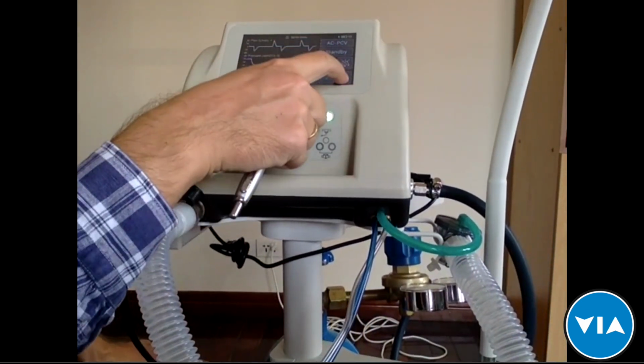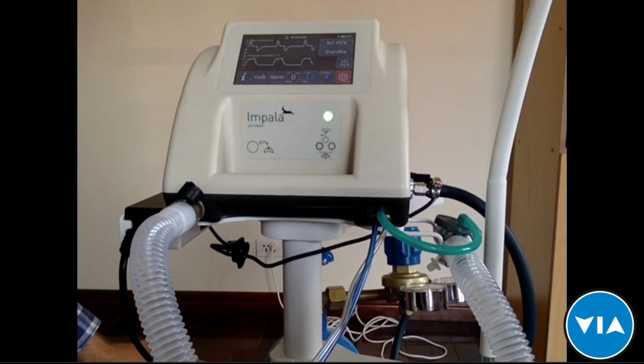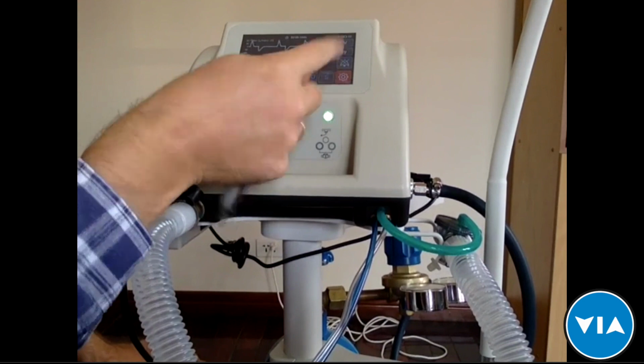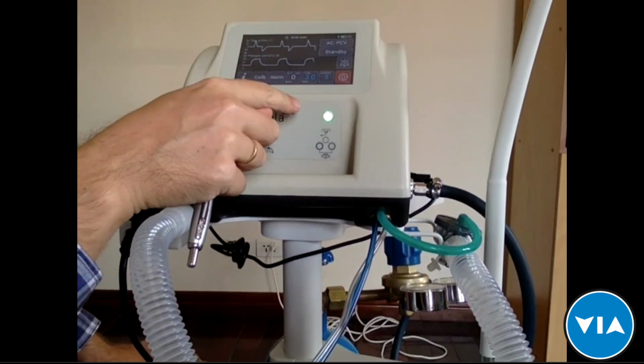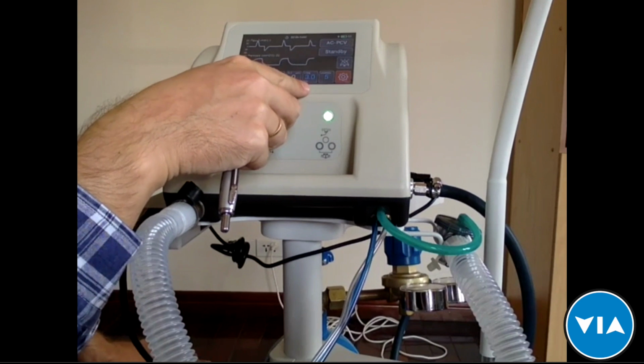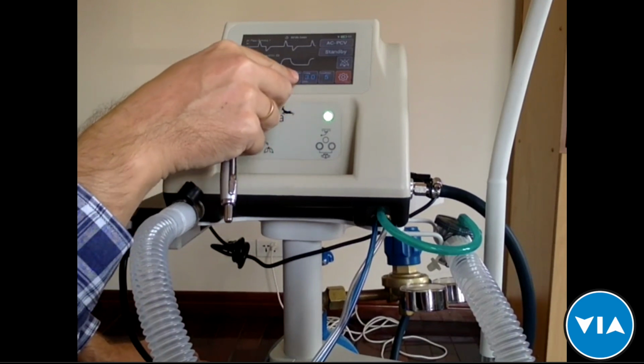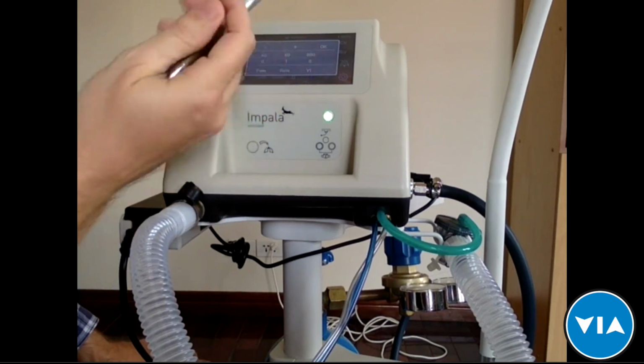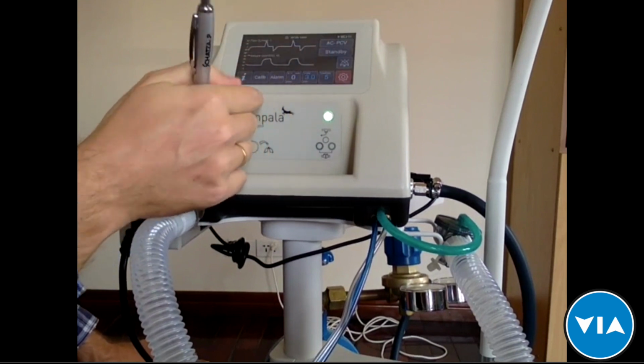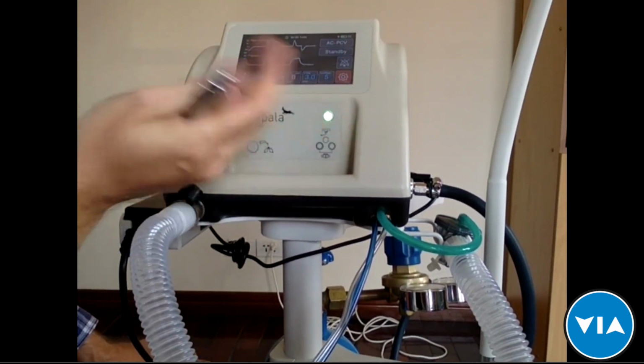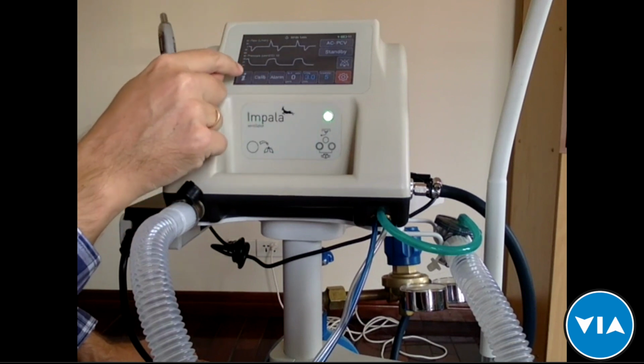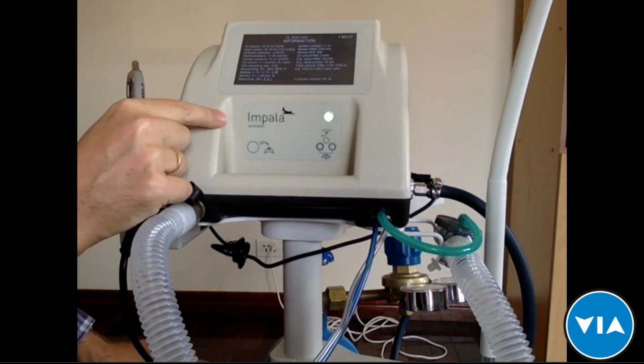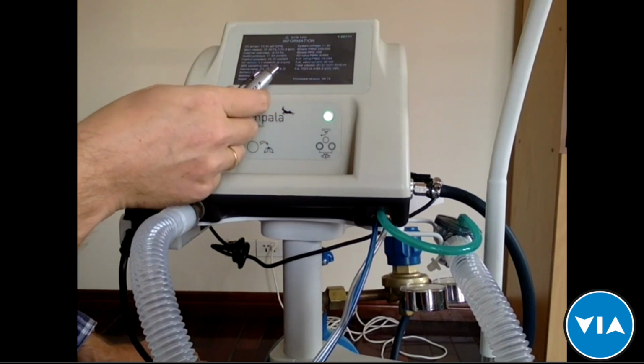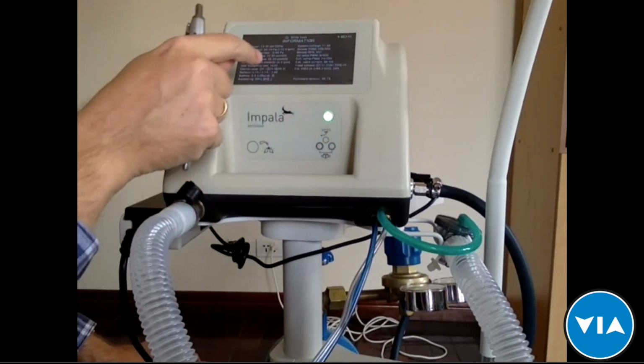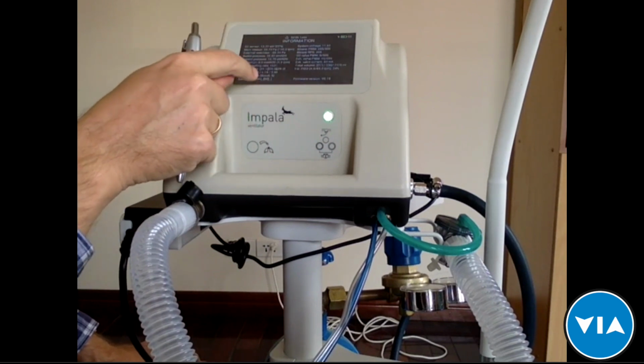There are additional functions. Obviously, you can go to the functions: how loud the device should be, so loudness, then the volume trigger ratios and breaths per minute, and set the alarms if you want. That's quite interesting, when they are going to be activated. And calibration, you can perform calibration while the device is on. For more detailed information, there is plenty. This is diagnostics. So there's a diagnostic screen which will communicate in case something is happening, as a serviceman or distributor.